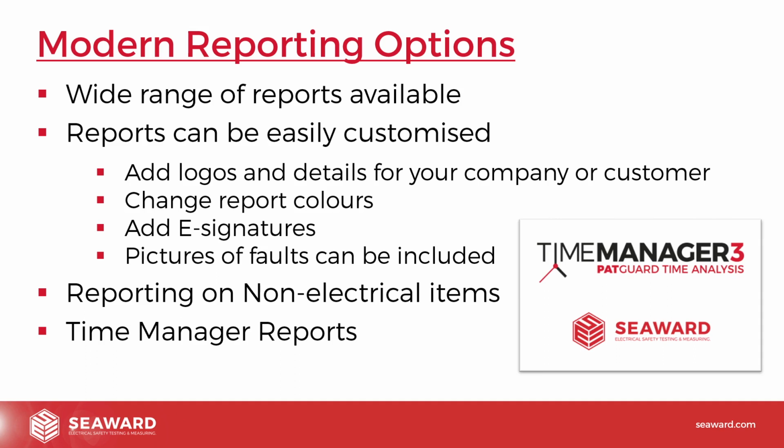Whereas if you saw that somebody turned up at 10 o'clock in the morning, did 200 tests between 10 and 11 o'clock, and then there's no test for the rest of the day, that would give you an idea that person had just come in and maybe just connected up a lead and just kept pressing pass, and done that. So it is very good for monitoring what's going on and making sure that the testing is actually being carried out correctly.